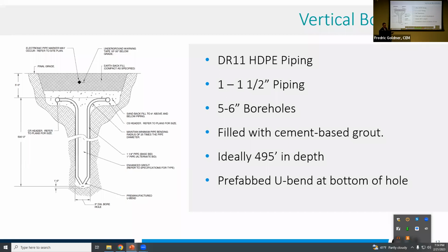Most drill rigs that do this work are well drilling rigs for potable water, so they're tooled for 6 inch. If you can find a 5 inch, great. Nobody's ever given me a rebate or a discount for using a 5 inch bit, and I've used even 3 inch bits as well. There's a perfect tool for every application, and I rely on my drillers to give me the feedback, and I respect them as the professionals of doing it. 1.5 inch piping, that's kind of a little bit on the large scale. I probably see 1.25 inches on a borehole like this, but I may use 1.5 inch. Typically for residential, you'll always see 3/4.